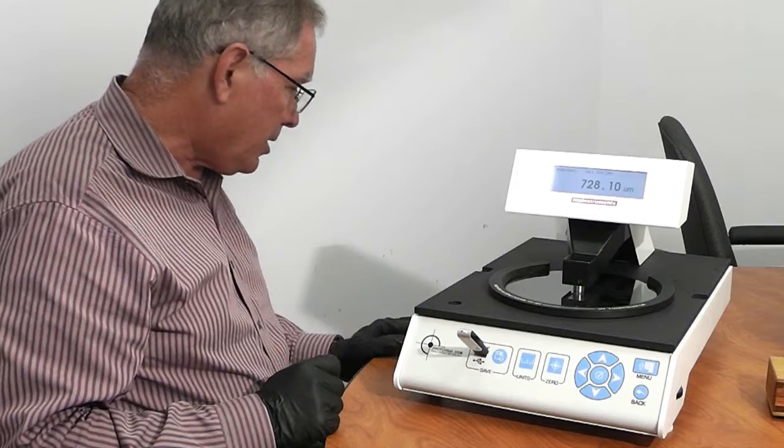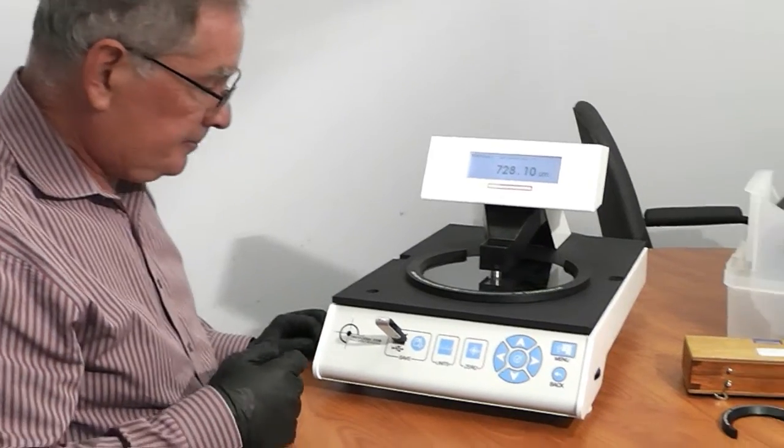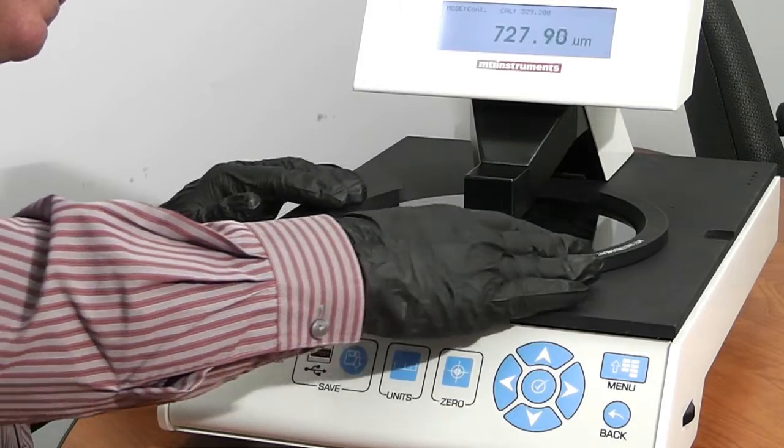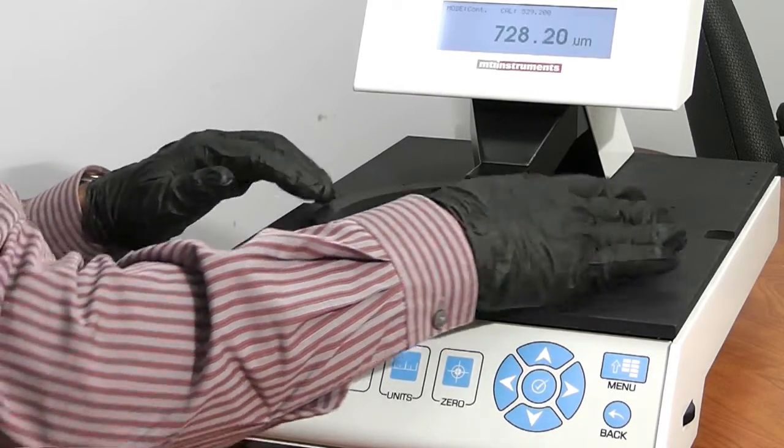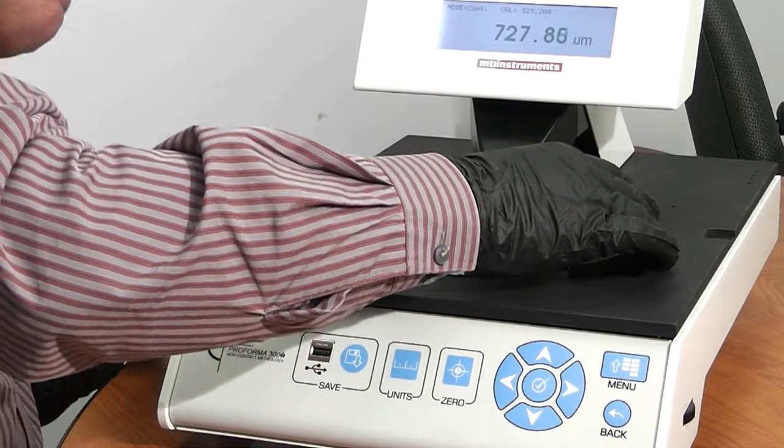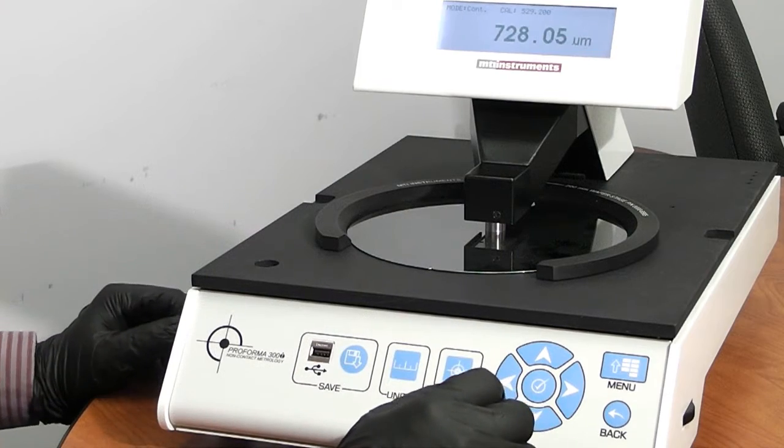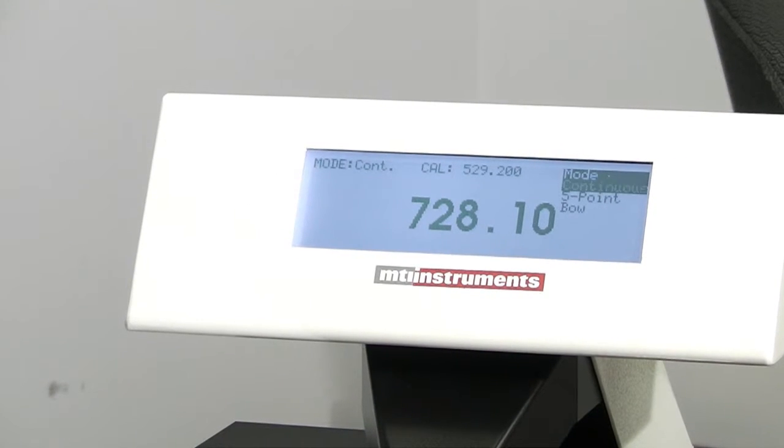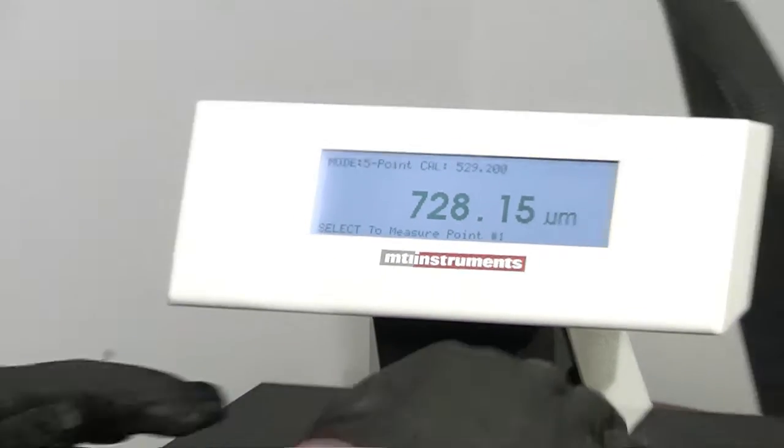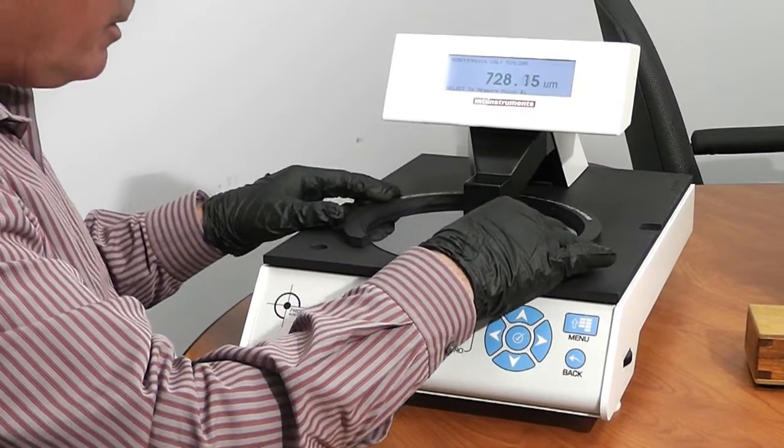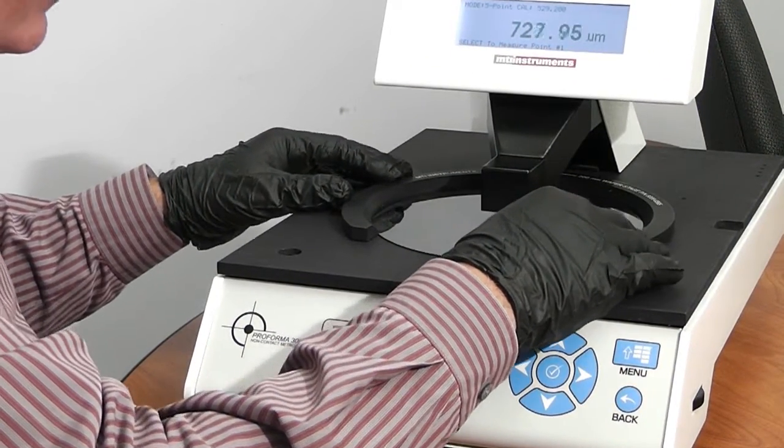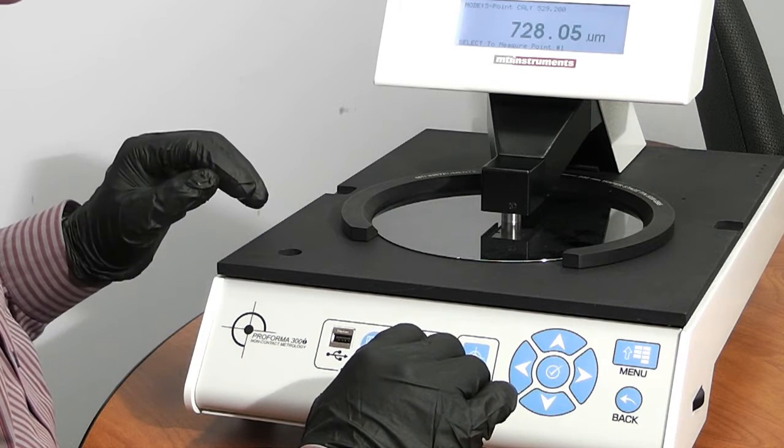The next thing we're going to do is we're going to measure the total thickness variation. So I'm going to take the thumb drive out. We'll stick with the same wafer here. So we're going to menu, and the next thing we're going to do is select mode, and we're going to do five point. So ideally what we do is we would set the pins, but just to show you quickly how we work this is we're going to look at five points around the wafer, and we're going to save these, and then it'll calculate the total thickness.